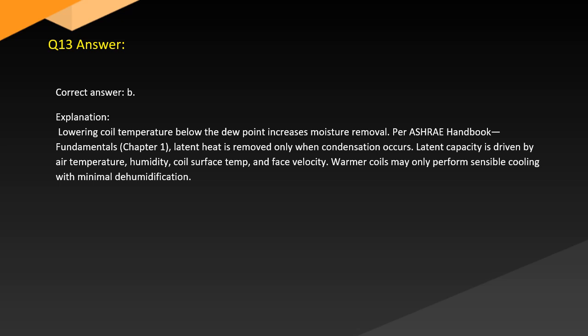Answer. Correct answer: B. Explanation. Lowering coil temperature below the dew point increases moisture removal. Per the ASHRAE Handbook, Fundamentals, Chapter 1, latent heat is removed only when condensation occurs. Latent capacity is driven by air temperature, humidity, coil surface temperature, and face velocity. Warmer coils may only perform sensible cooling with minimal dehumidification.